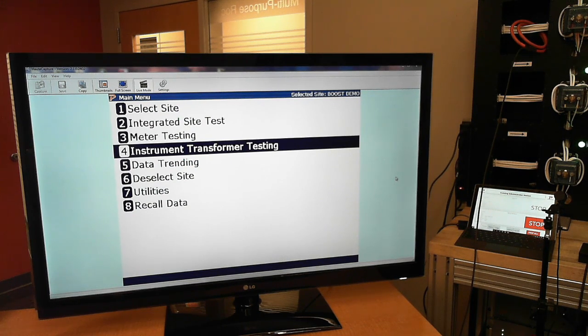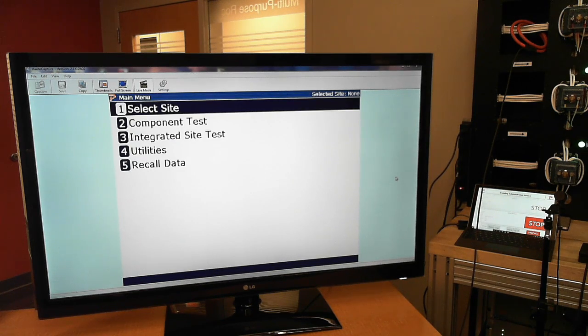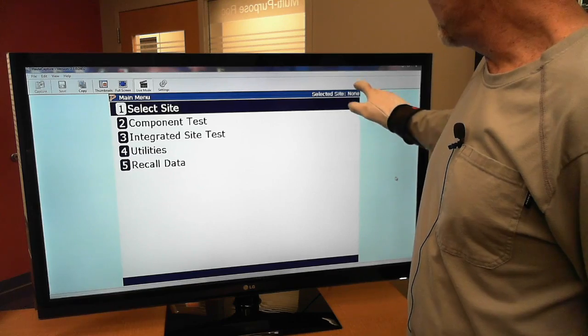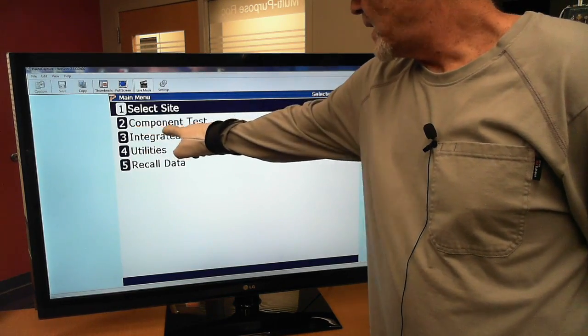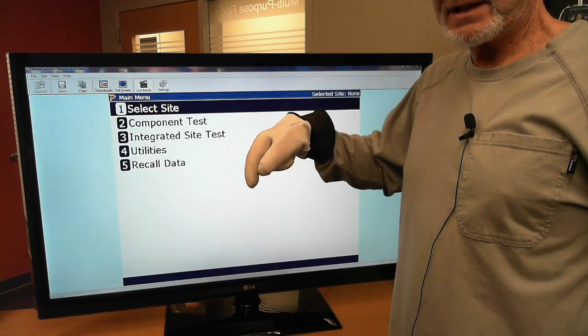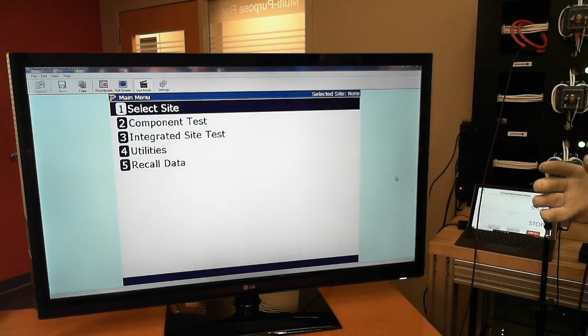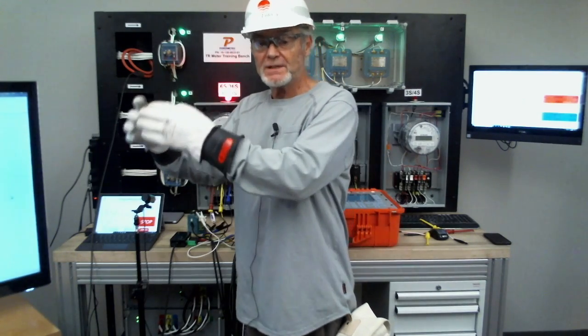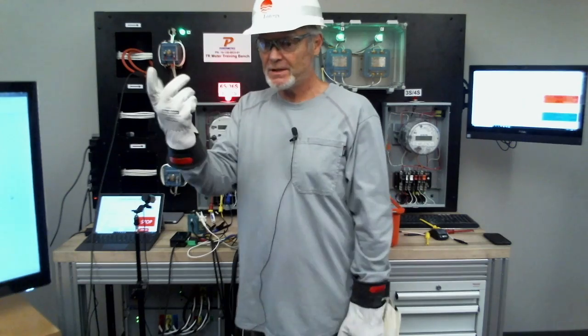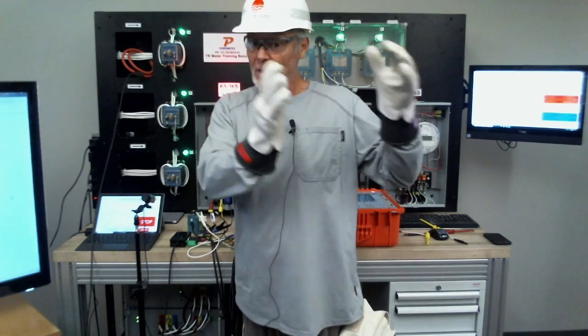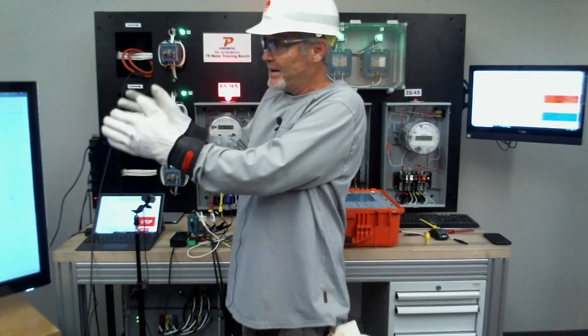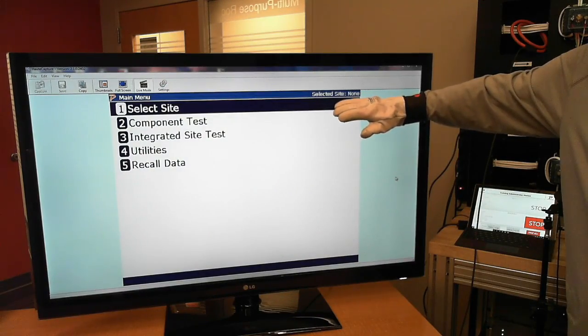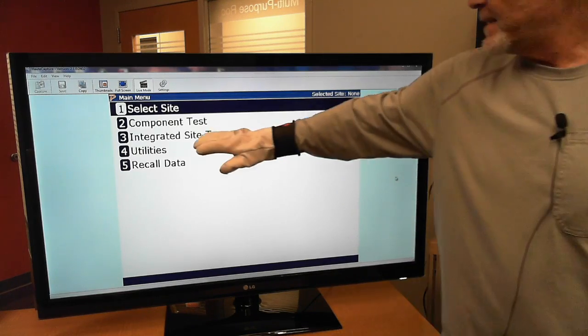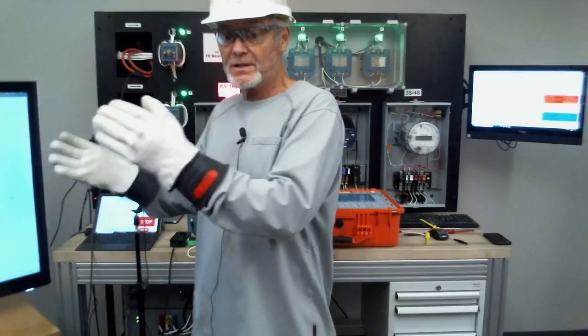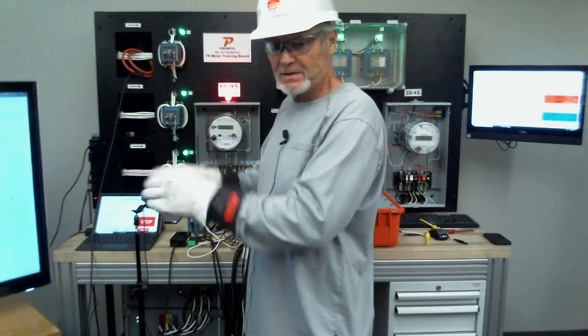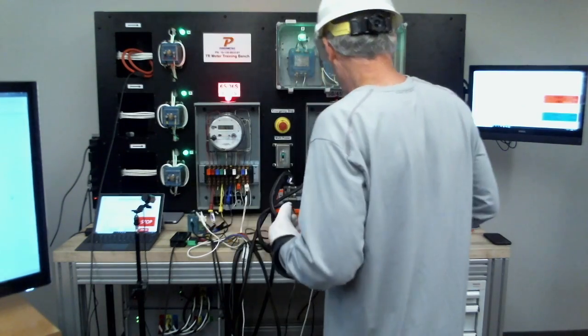I'm going to deselect the site, number 6. So I deselect the site, it takes me out to my main menu, and when I get there, I don't have a site selected. It offers me the choice of component test. The component test is how you do the benchtop test. If you think about it, a load boost test is associated with a site—I'm out at a site. A benchtop test is just a CT sitting there in the shop that you want to test; it's not associated with a site, so it goes to a different part of the menu. I don't go to the site-associated menu anymore, which you'd normally see in the upper right-hand corner. I come back out to my main menu, which gives me this component test option, so I can test something that's not associated with a site—just a CT sitting on the bench, like what we're doing right now. So I'm going to go ahead and choose component test, number 2.